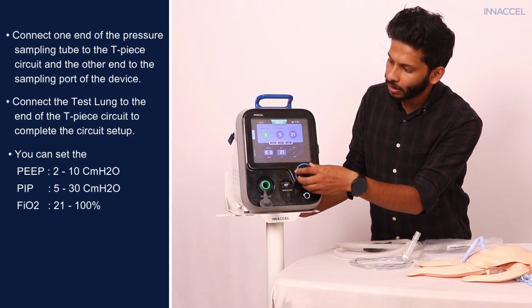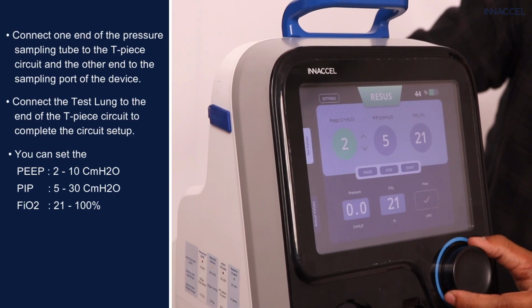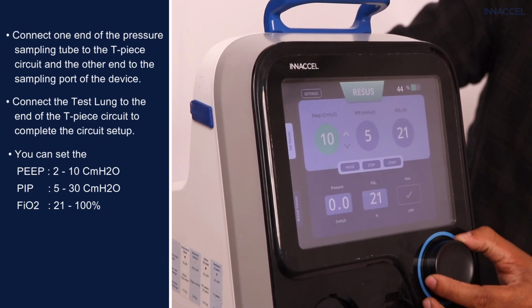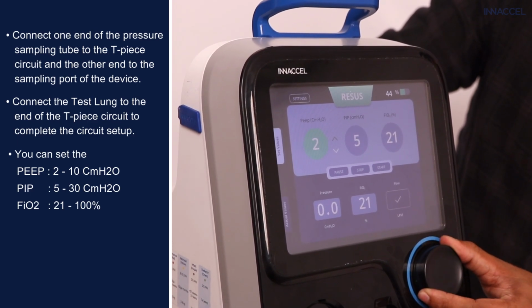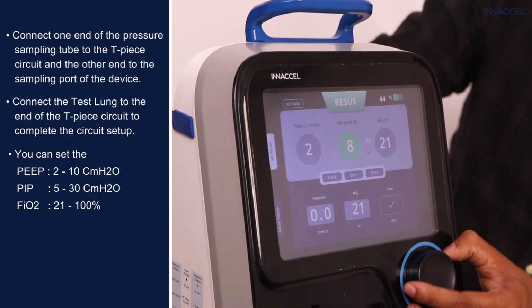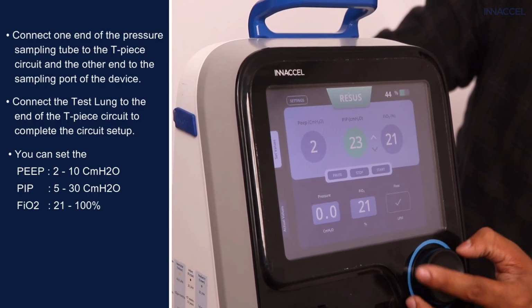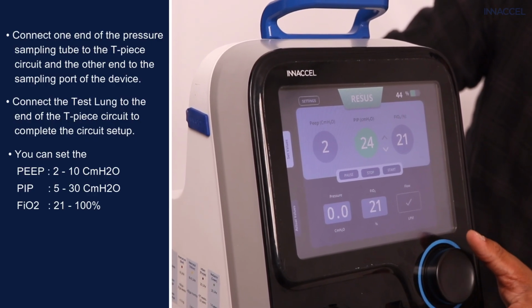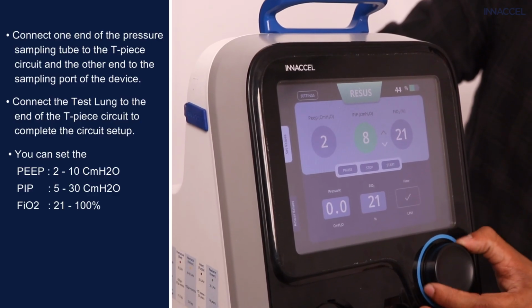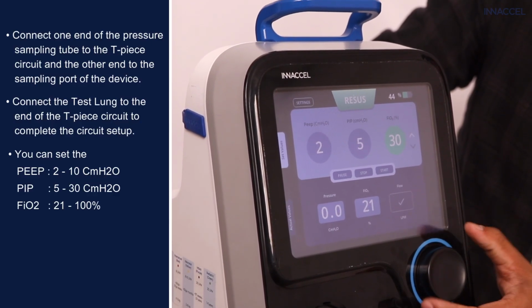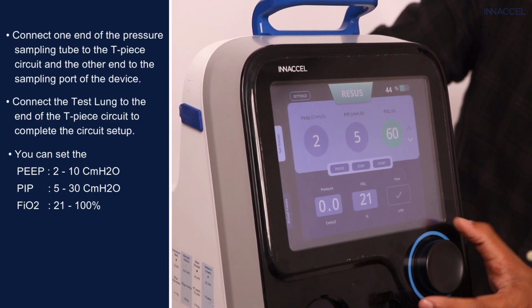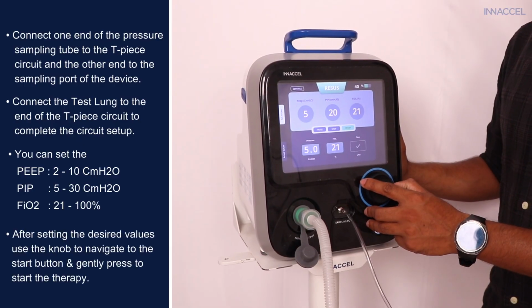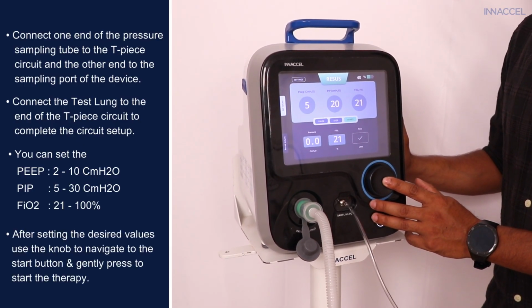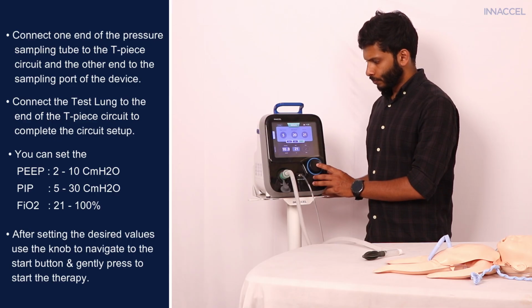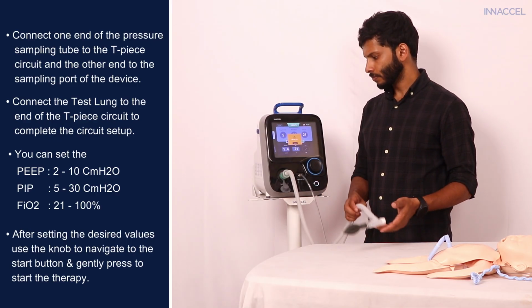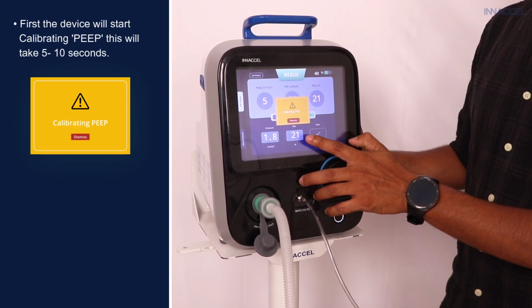You can set the PEEP between 2 to 10 centimeters of water, PIP between 5 to 30 centimeters of water, and FiO2 between 21% to 100% as required. After setting the desired values, use the knob to navigate to the start button and gently press to start the therapy. First, the device will start calibrating PEEP.